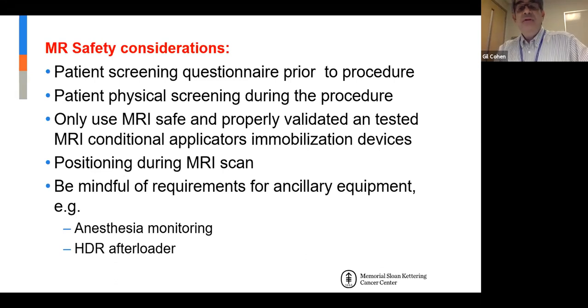Be mindful of ancillary equipment requirements. If you consider doing a procedure under anesthesia, the anesthesia monitoring system has to be placed outside a certain Gauss line, and that may vary with the machine you're using in the MRI. The same applies to the HDR afterloader - if you have your MRI and HDR in the same room, you need to make sure the afterloader is far enough from the magnet that it operates correctly and that everything is compliant with the IFUs of both the afterloader and the MRI.